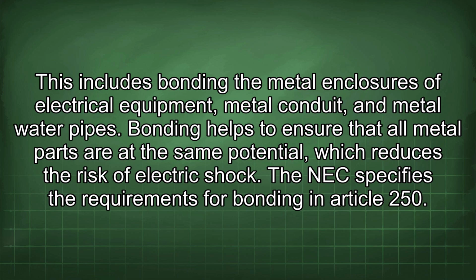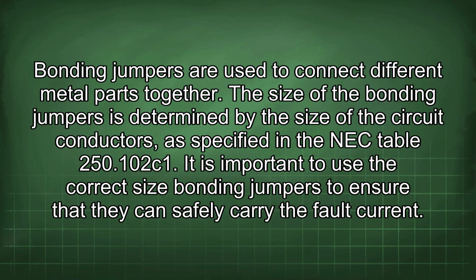The NEC specifies the requirements for bonding in Article 250. Bonding jumpers are used to connect different metal parts together. The size of the bonding jumpers is determined by the size of the circuit conductors, as specified in the NEC Table 250.102.